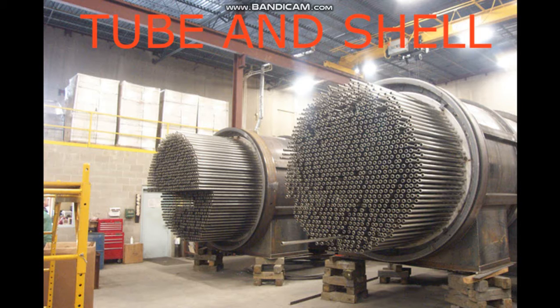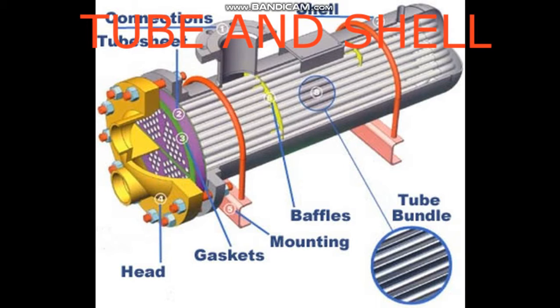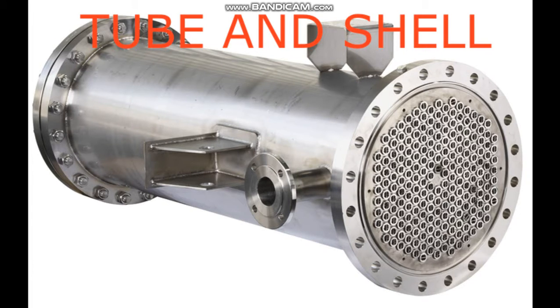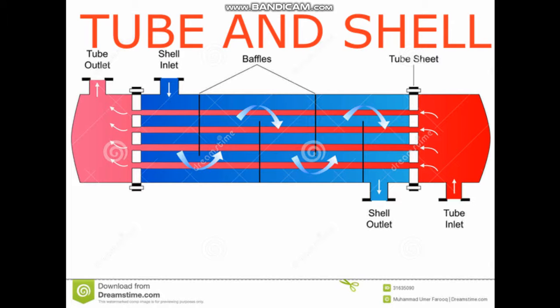The tube and shell heat exchanger is the most basic and most common type. It consists of tubes in a container, called a shell. Tube fluid is separated from the shell side fluid by the tube sheet. Tubes can withstand higher pressure than shells. Support plates act as baffles, directing the flow of fluids.